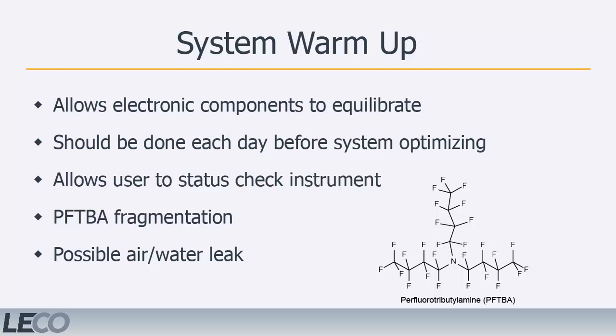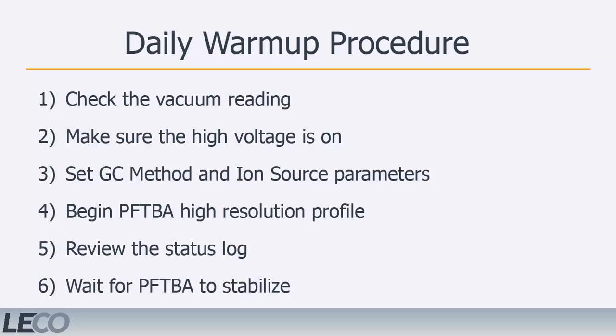For the Pegasus GC-HRT to function correctly, the electronic components inside it must be allowed to equilibrate. This process, also referred to as system warm-up, must be done at the beginning of each day prior to optimizing the instrument. Conducting a system warm-up also provides an opportunity for the user to determine the status of the instrument. This can be accomplished by monitoring the stability of the fragmentation of perfluorotributylamine, or PFTBA, to check for an air leak and possible contamination. The following is a summary of the system warm-up procedure to be performed each day.